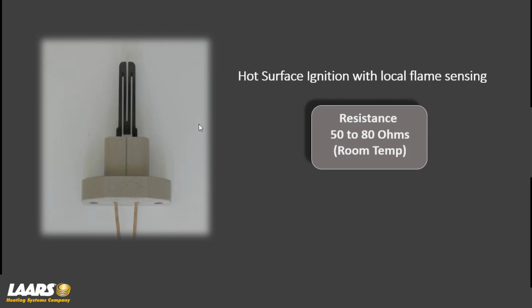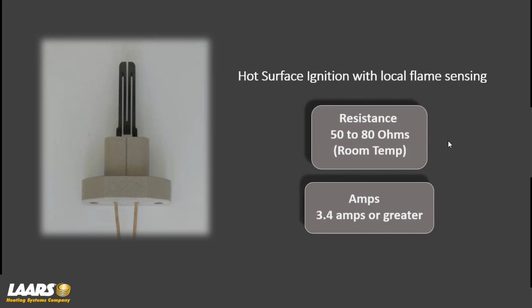So hypothetically, I'm going to refer to the MightyTherm2. You've got a weak igniter. It's glowing cherry red, but you're not getting your flame sensing, and it drops out, goes into lockout. There's a reset button on the Fenwal control that we'll see in a minute. You can press the reset button. Now, however, if it starts glowing cherry red again, gets hot, it's no longer at room temperature. So there's also another way to check these, and that's with an amp probe, and you can check it with amps. That's pretty much what most Laars technicians, service managers utilize is an amp probe, and we're looking for 3.4 amps or greater. Typically, a good igniter or a new igniter starts around 3.8 to 4.2 as your amp draw. So we start getting below 3.4 amps, we're going to start to see ignition failures. Ignition lockouts. They're getting weak.